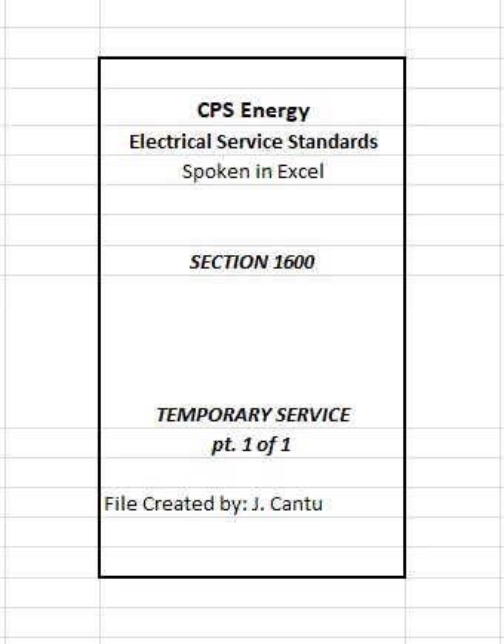1604.1 Location of temporary meter structure. The structure shall be located within the customer's premises at a minimum distance of 15 feet and a maximum distance of 100 feet from CPS Energy's main line pole with a maximum load of 25 kVA. Working clearances about temporary meter loop equipment shall be in accordance with Section 1800.